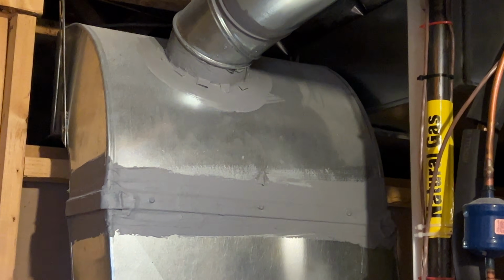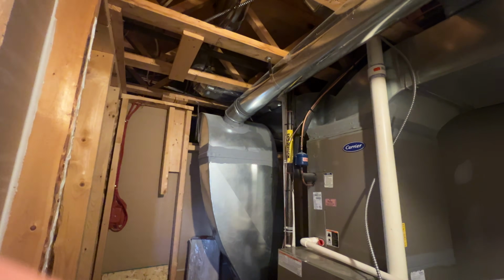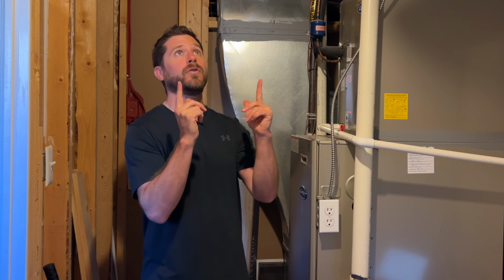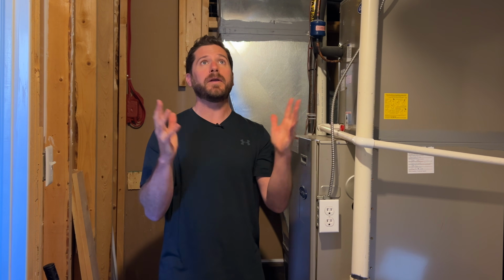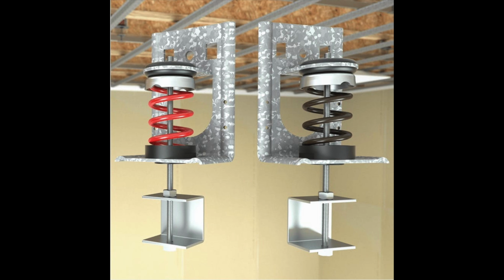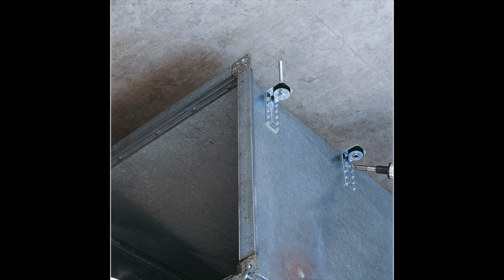What you can do to minimize or eliminate that vibration, if you can access your air duct system with an open ceiling, is change those brackets — but be careful to change just one at a time. These types of brackets create a gap between the air duct and the joist, so all the vibration stays in the air duct and doesn't transfer into the joist, your home, and the structure.